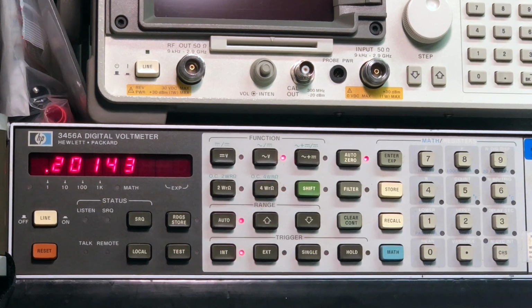So there's 200 millivolts, 300 millivolts, 400, 500 millivolts, half a volt right there. That's looking very good. So again, that's 0.50 on the DS340 display. So that's being reflected over there on the digital voltmeter. Very good. 600 millivolts, 700 millivolts, 800 millivolts, 900. Yep. And now on the DS340 it says 1.00. All right, for 1 volt, and that accuracy looks spot on.